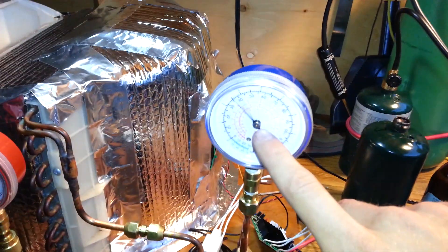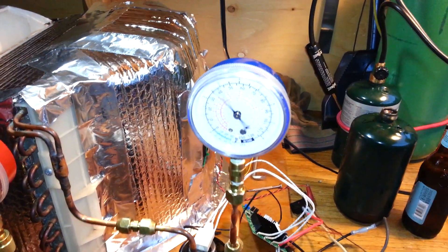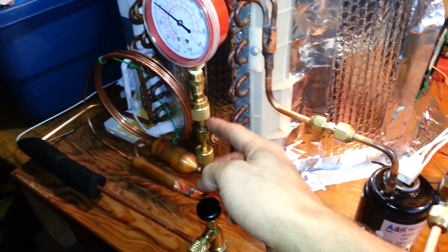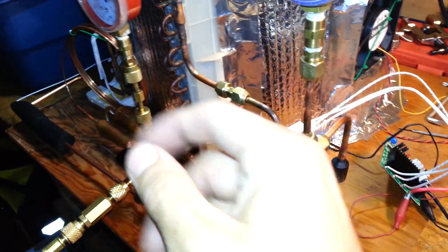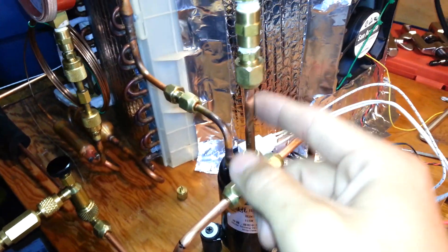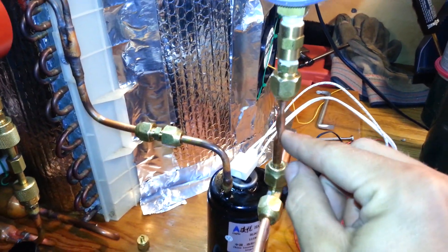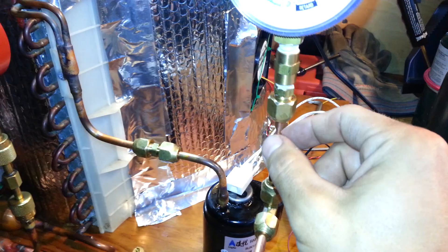Oh, one other thing. I'm still having some issue with the fluttering on my low side. I discussed that in a previous video. I replaced what was a brass finger-tight arrangement with a copper flare system. You can see that I pinched it there. Still was getting some fluttering, so I pinched it again.